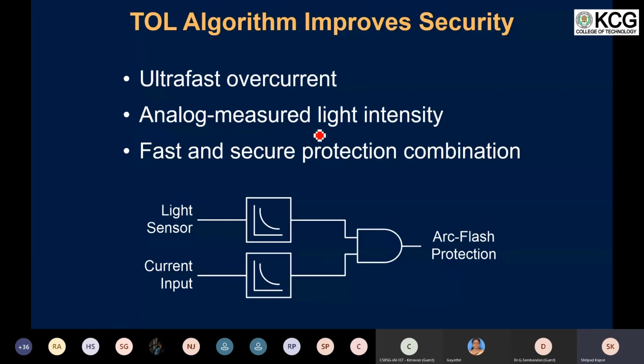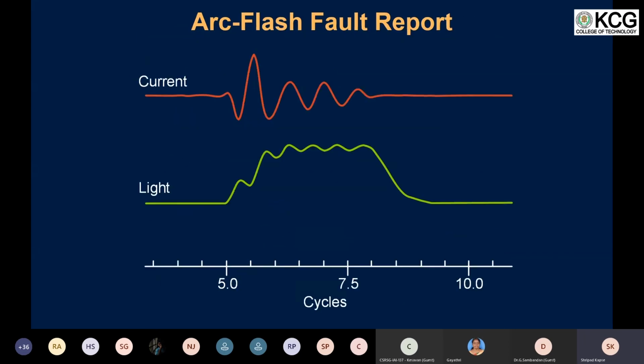And we are going to measure the intensity of light sensed by the sensor as an analog quantity, and using the combined approach of both the light and the current, we are going to provide protection for an arc flash fault. So if you look at the overall operating time in this case, with this novel approach, we are getting an operating time of as fast as 2 milliseconds. So this is much faster compared to all the other previous schemes that we saw earlier.